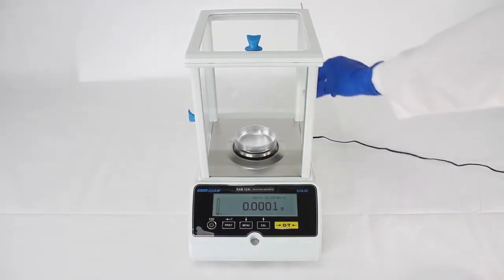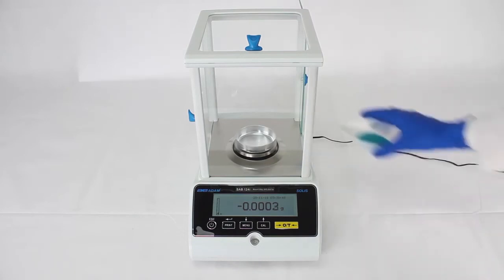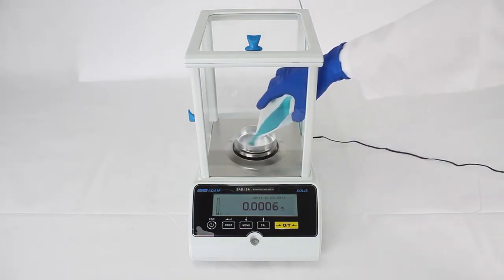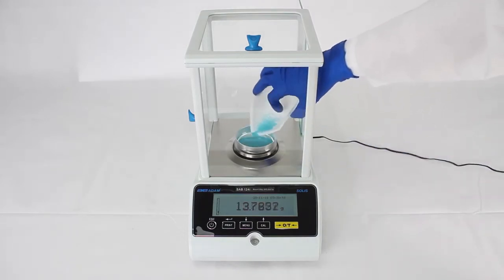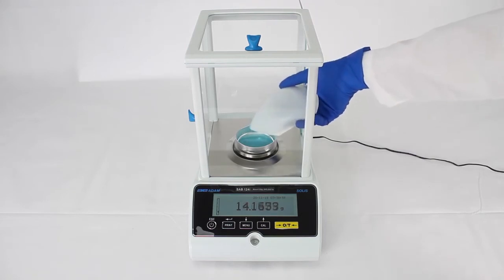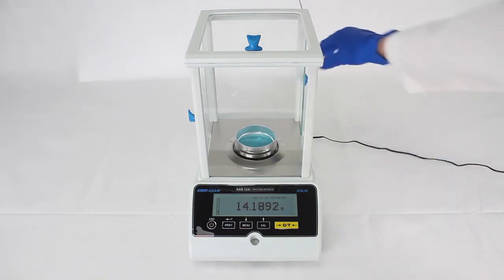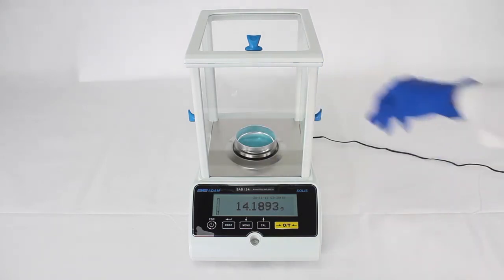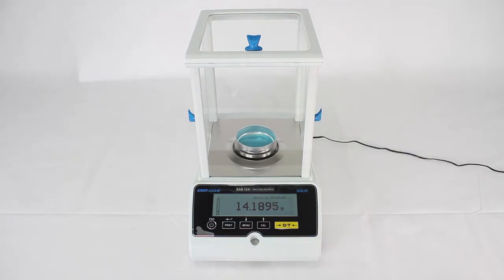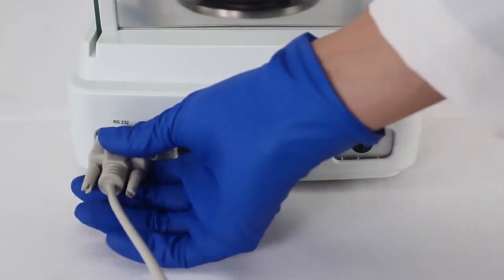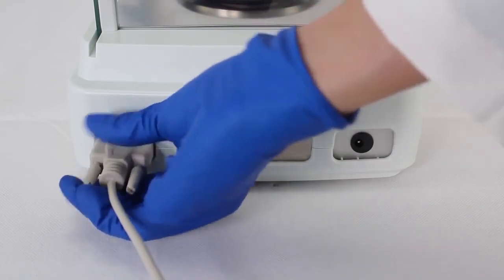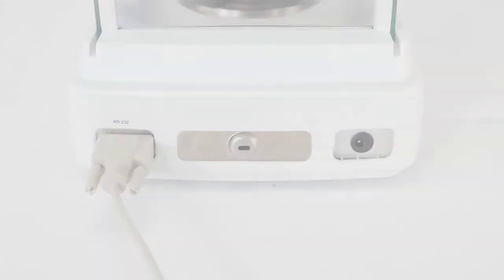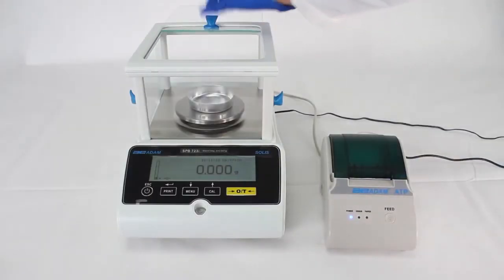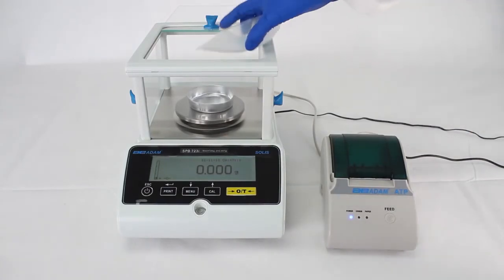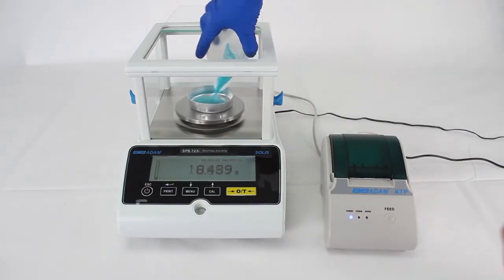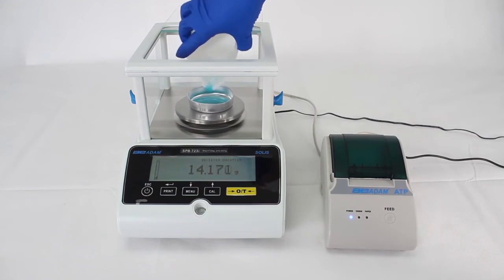Semi-micro, analytical, and milligram models have draft shields with sliding glass doors. This boosts accuracy by eliminating the effects of breezes and reducing static electrical interference with the balance. An RS-232 interface is included for speedy connection to computers and printers. Printouts provided by the balance include date and time, essential for traceability and data tracking within good laboratory practice guidelines.